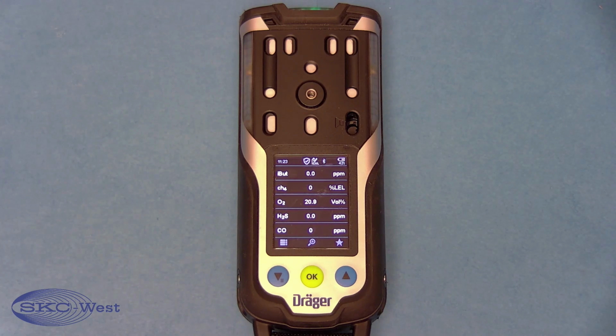Bump testing is a critical process that ensures your monitor will alarm if exposed to the gases your monitor is configured to detect. Bump testing can take place manually or preferably on the X-Dock. Today we're going to go over the manual process. To get started, you want to connect the gas cylinder with a fixed flow regulator that is 1/2 a liter per minute to the calibration adapter.